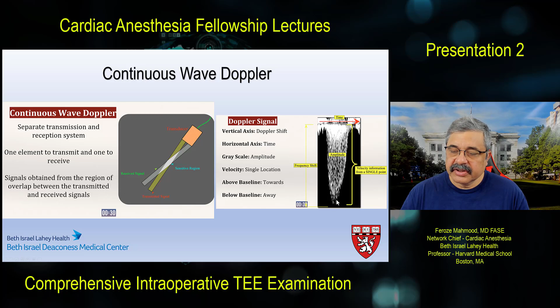Now, if you look at the Doppler profile, it's like a velocity time integral envelope. The vertical axis demonstrates the Doppler shift, the horizontal axis demonstrates the time, and the grayscale, which means how intense it is, represents the amplitude of the signals, or the number of RBCs that have been interrogated. Velocity is the peak velocity at a single location, of which we are not certain where exactly it is happening in this entire angle of interrogation. When it is above baseline, it is moving towards, and when it is below the baseline, it is moving away from the transducer. So that's what the signal profile of a continuous wave Doppler looks like.